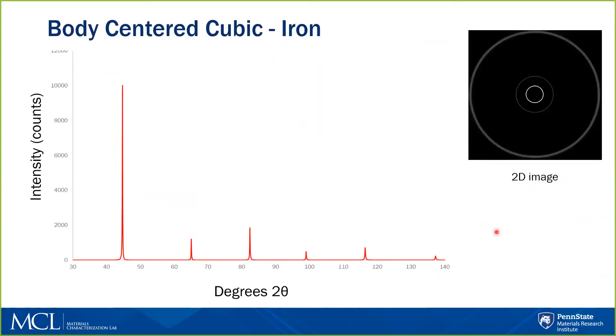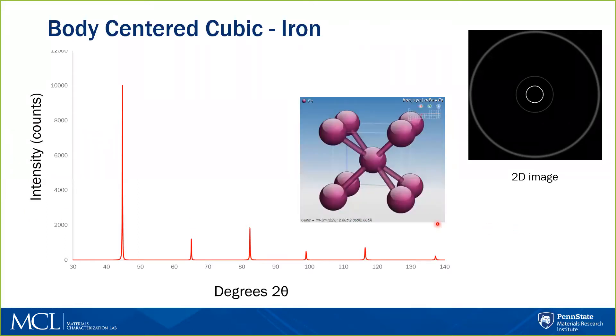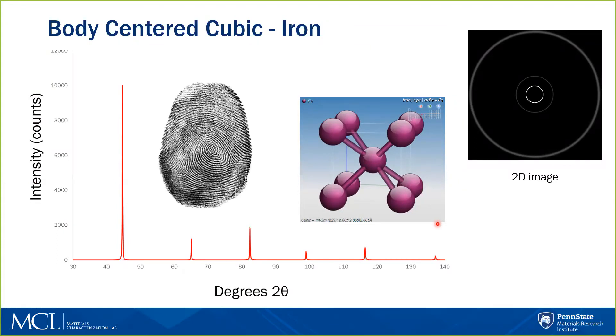Constructive interference occurs when Bragg's Law is satisfied at some particular angle and some particular distance or d-value. That constructive interference is reported or detected in two different ways. If you're using a system that uses a 2D image detector, you'll get an image that looks something like this for a randomly oriented powder material. Or if you're using a system which directly plots the data, you'll get a 1D plot of degrees 2 theta on the X-axis and intensity in counts or counts per second on the Y-axis.